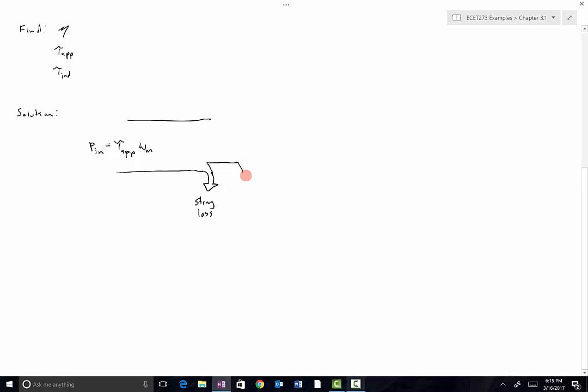Then what we've got is something called friction and windage loss. So the thing's spinning, so not all the torque gets converted into actual rotation. The spinning creates some friction, so that's friction and windage loss. And that reduces total power even more.